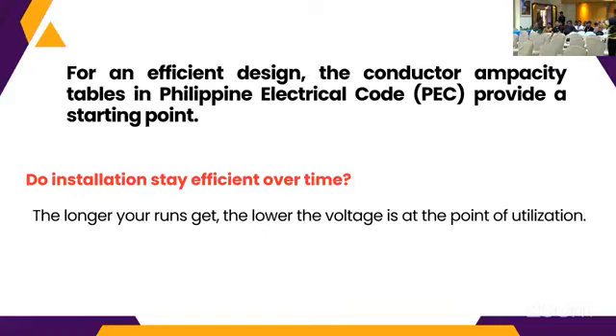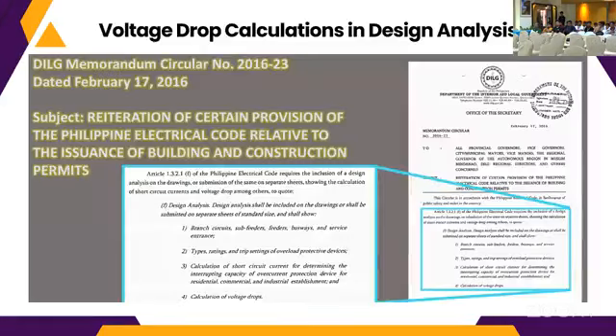Reduce voltage, so small voltage. Why? Because of the voltage drop. Malayo siya (it is far). Okay? The next. So voltage drop calculation is in design analysis. This is part of the requirement of the Office of the Building Official. So kailangan po natin, from the DILG Memorandum Circular number 2016-23 dated February 17, 2016. Subject: reiteration of certain provisions of the Philippine Electrical Code relative to the issuance of building and construction permits. So nandito yan sa number 4, sa design analysis, calculation of voltage drops. Okay? So that is required.